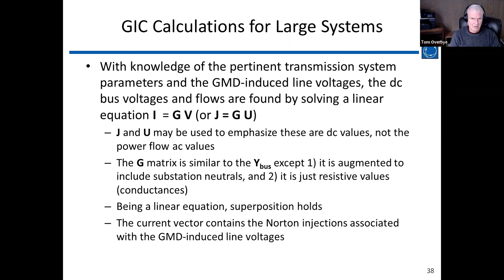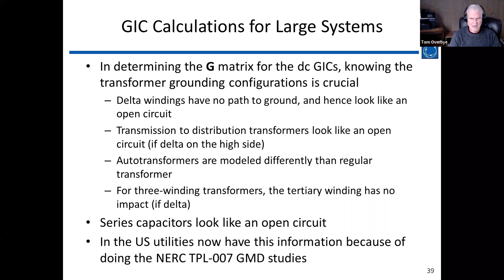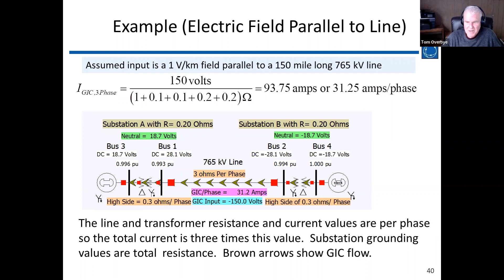There are some issues you have to go through, like delta windings, transmission and distribution transformers, and so on. But because NERC requires utilities to do GMD studies, they all have this information and are using it, so it's now available and we don't have to dwell on that. This is a simple example of calculating the GICs. It's really just solving DC circuits, and if you're used to doing power flows on AC systems, it's actually much easier because it's DC. This is something PowerWorld has built in.